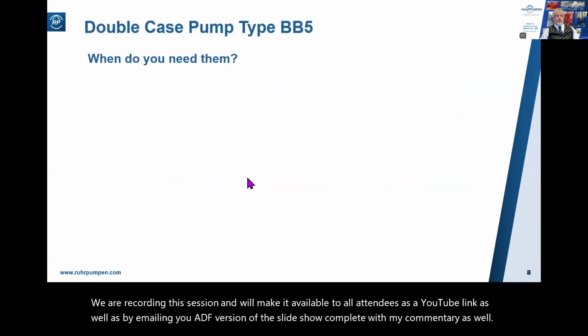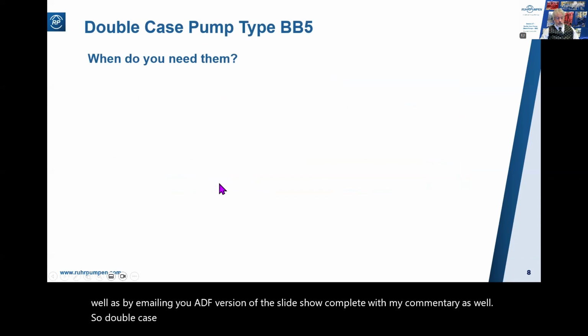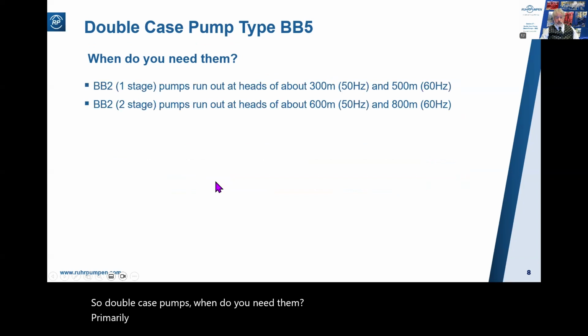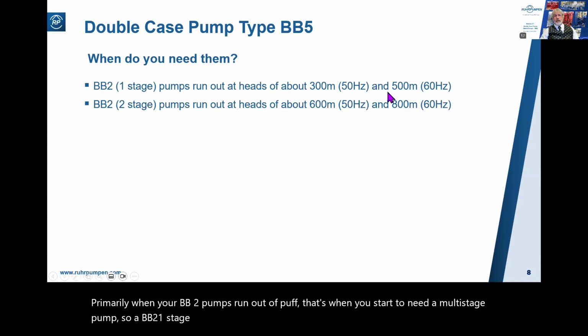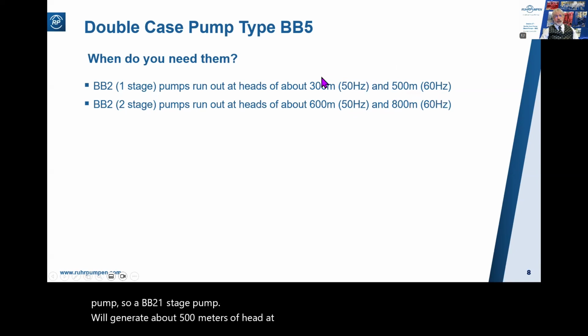So double case pumps, when do you need them? Well, primarily when your BB2 pumps run out of puff. That's when you start to need a multi-stage pump. So a BB2 one-stage pump will generate about 500 meters of head at 60 hertz, 300 meters at 50 hertz.